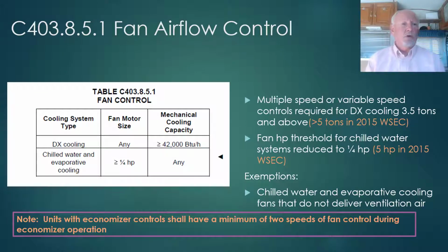And then the last control item we're going to touch on here is fan controls. In the previous code, the 2015 Washington State Energy Code, multi-speed or variable speed fan controls were required on DX cooling systems greater than 5 tons. That scope has been reduced to 3.5 tons and above. So 3.5 tons and above, DX cooling, package or split, now requires multi-speed or variable speed fan controls.